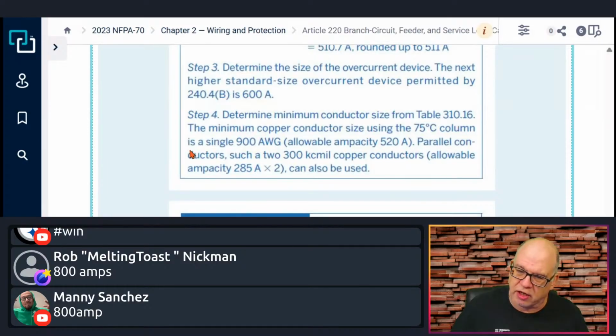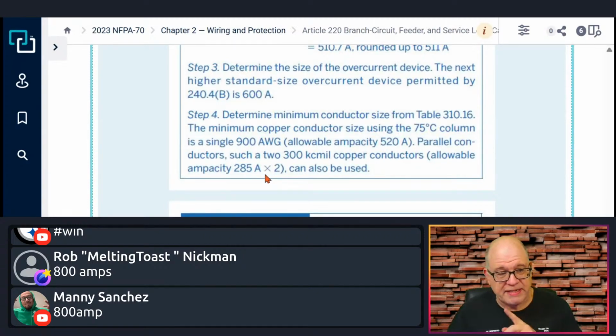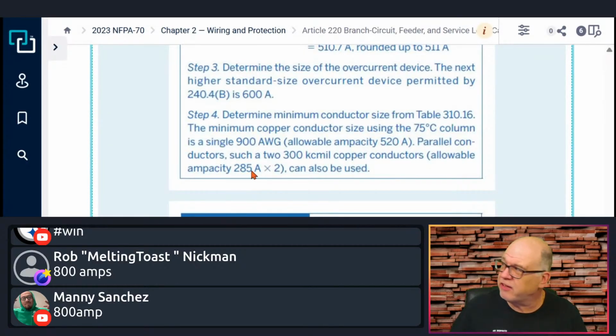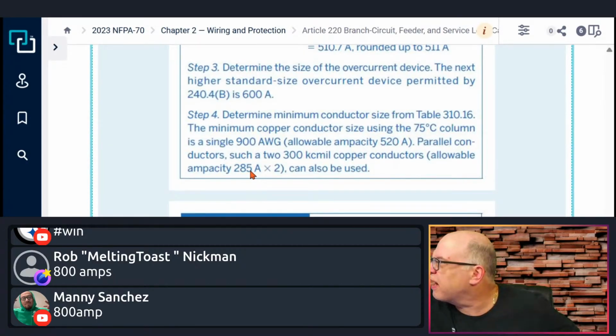So parallel conductors, such as two 300 kcmil copper, allowable ampacity is 285 each. Running them in parallel, following all the rules in 310.10, the paralleling rules, then I'm going to have 282. Hold on for a second. I'm going to lose TikTok.